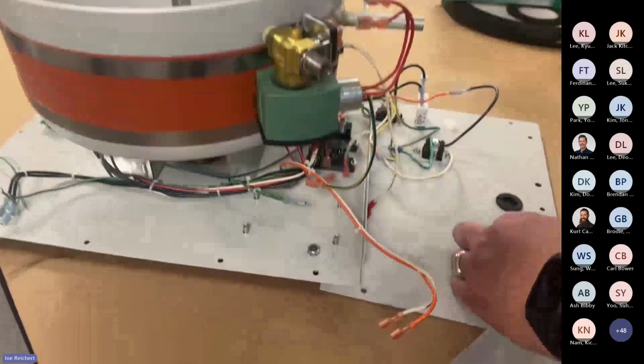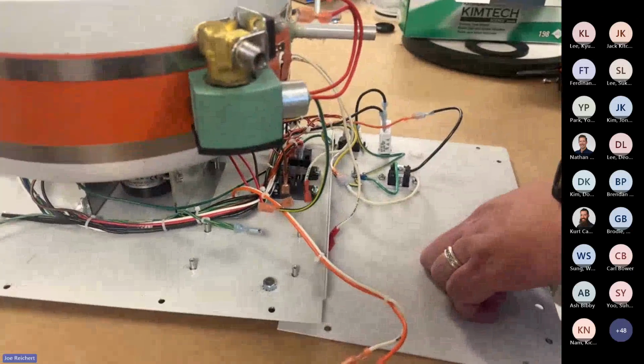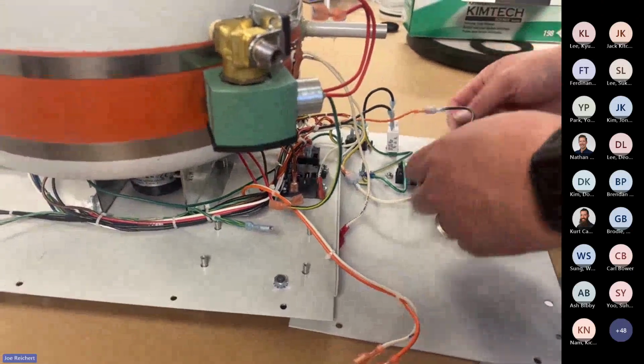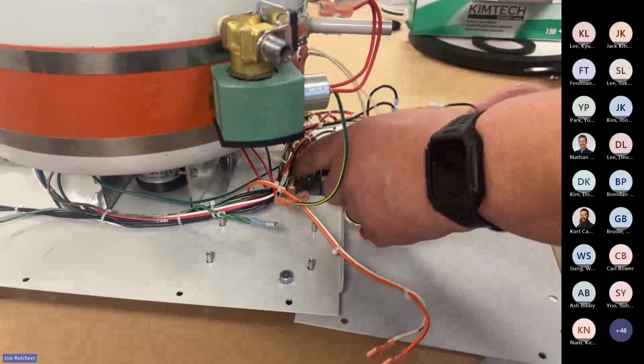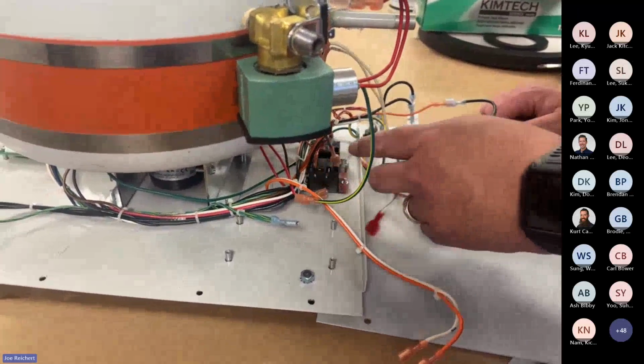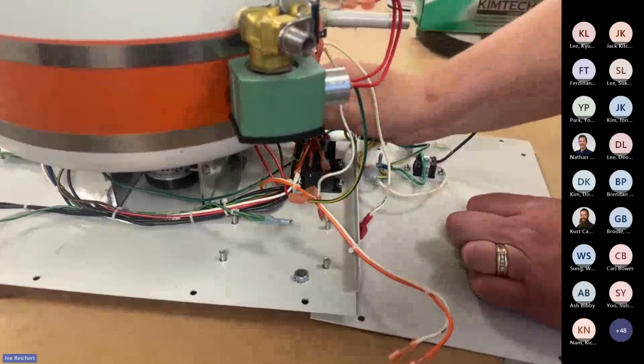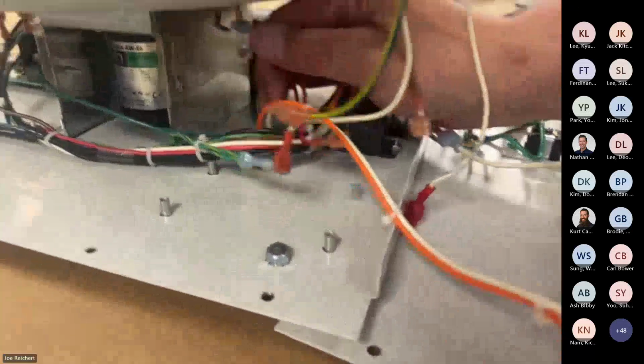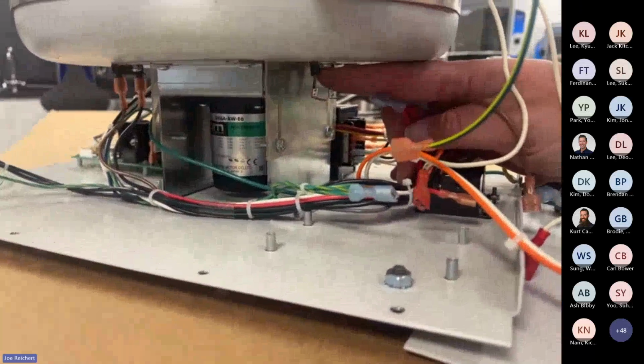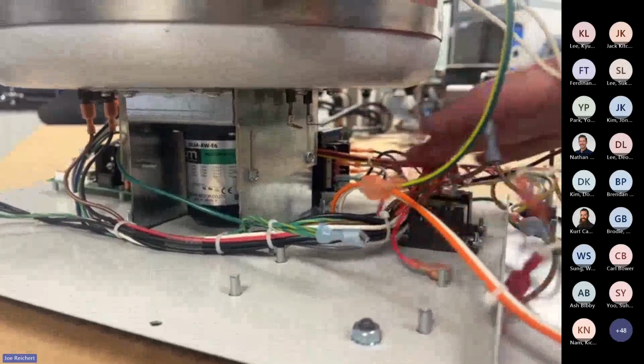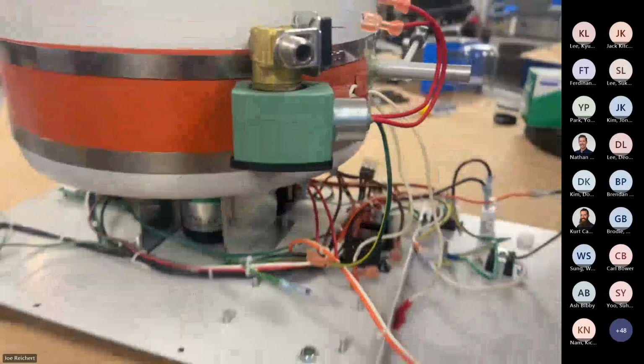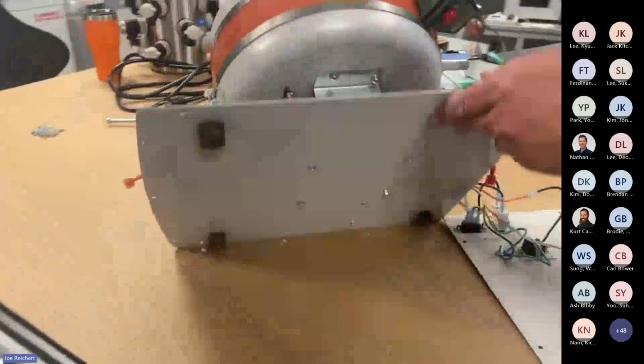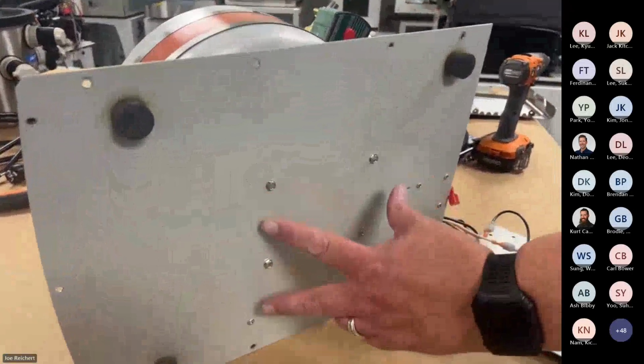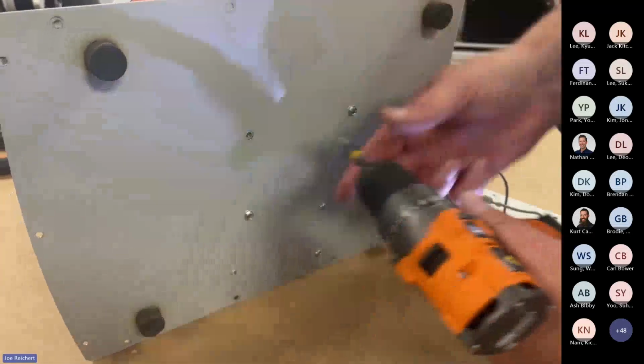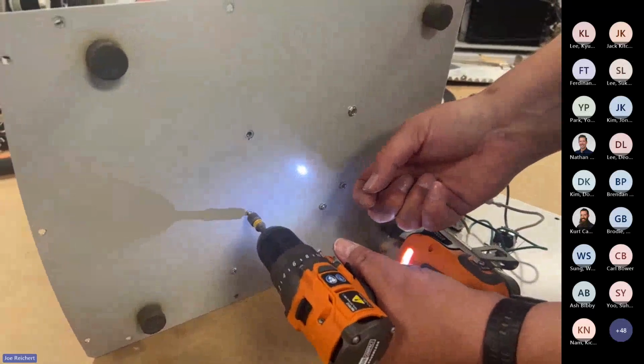It's always good to take pictures of all your wiring ahead of time so you know where everything goes before you take it apart. But you can also look at the wiring diagram and figure it out as well. And there's some that go to the heater coil up underneath. You have the heater terminals right here underneath it. Pull those wires off. And if you turn the unit on its side, got these 4 screws here that allow us to remove the chamber completely.